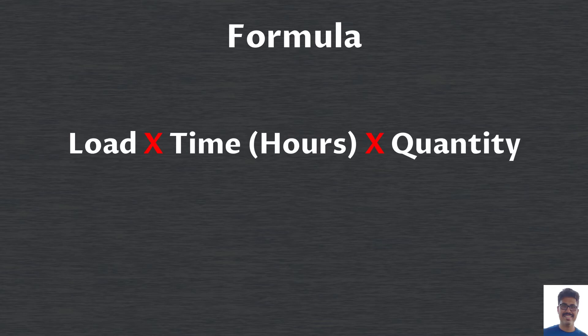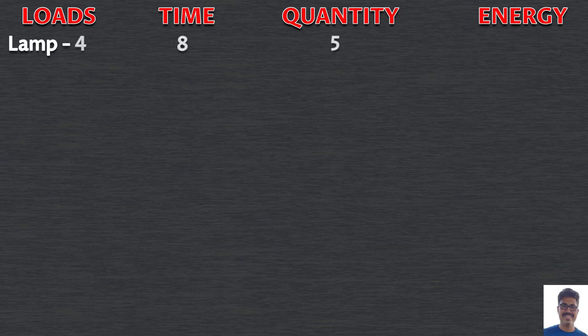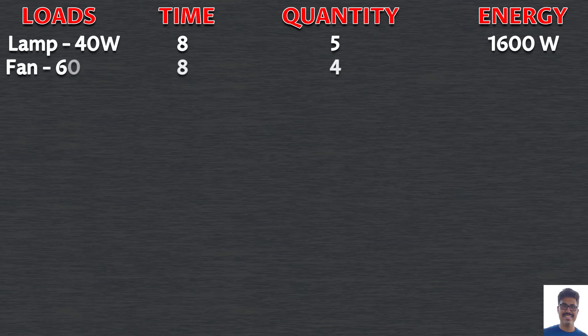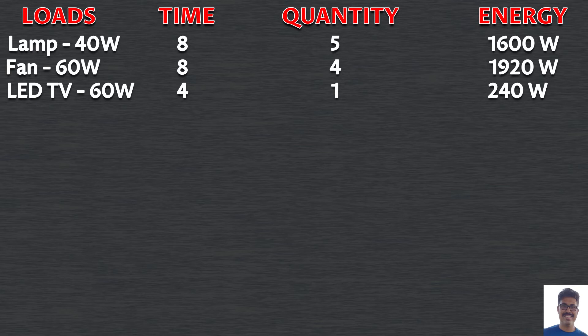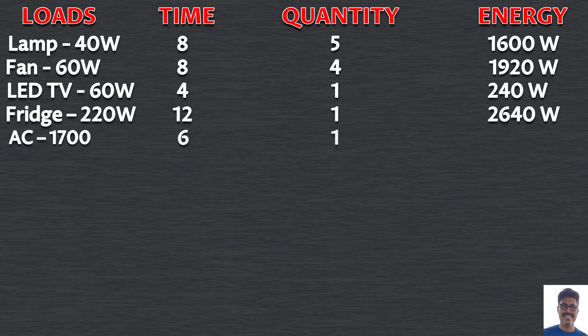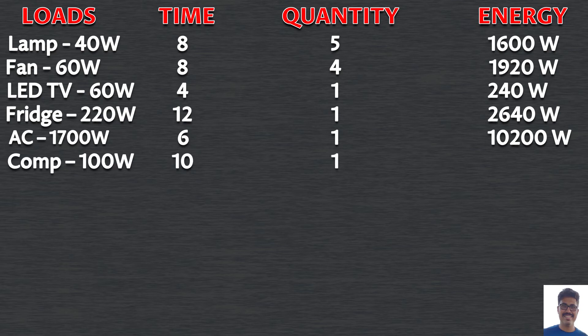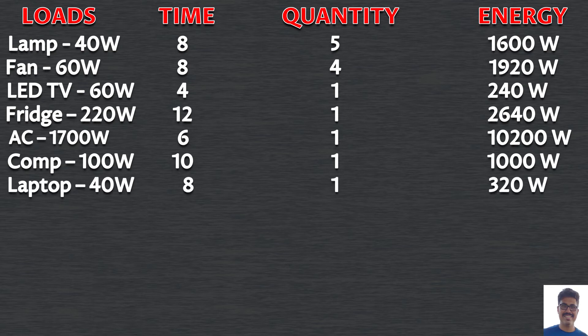The formula for total energy will be: load × time in hours × quantity. For lamps: 40 × 8 × 5 = 1600 watt-hours. For ceiling fans: 60 × 8 × 4 = 1920 watts. For TV: 240 watts. For refrigerator: 2640 watts. For AC, it will be much bigger — 10,200 watts. Desktop computer: 1000 watts. Laptop: 320 watts. You can pause the video, open a calculator, and add all the energy consumption values.